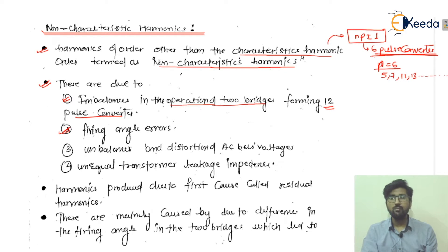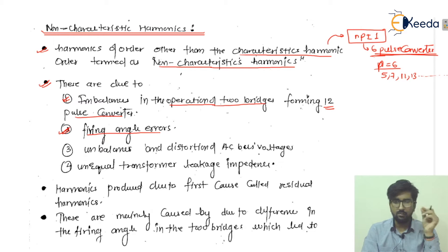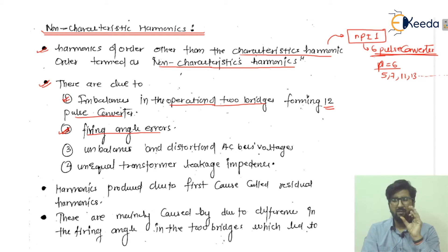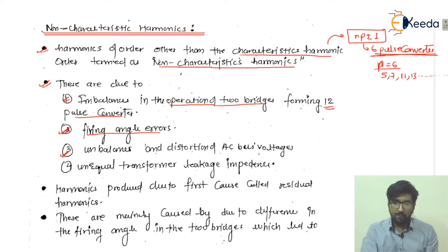The second cause is firing angle error. For example, one thyristor should operate at alpha = 30 degrees and the other at alpha + 30 degrees, since 30 degrees is the offset used in a 12-pulse converter. However, due to some disturbance or connection issues, if a firing angle error occurs, this can be a cause of non-characteristic harmonics.